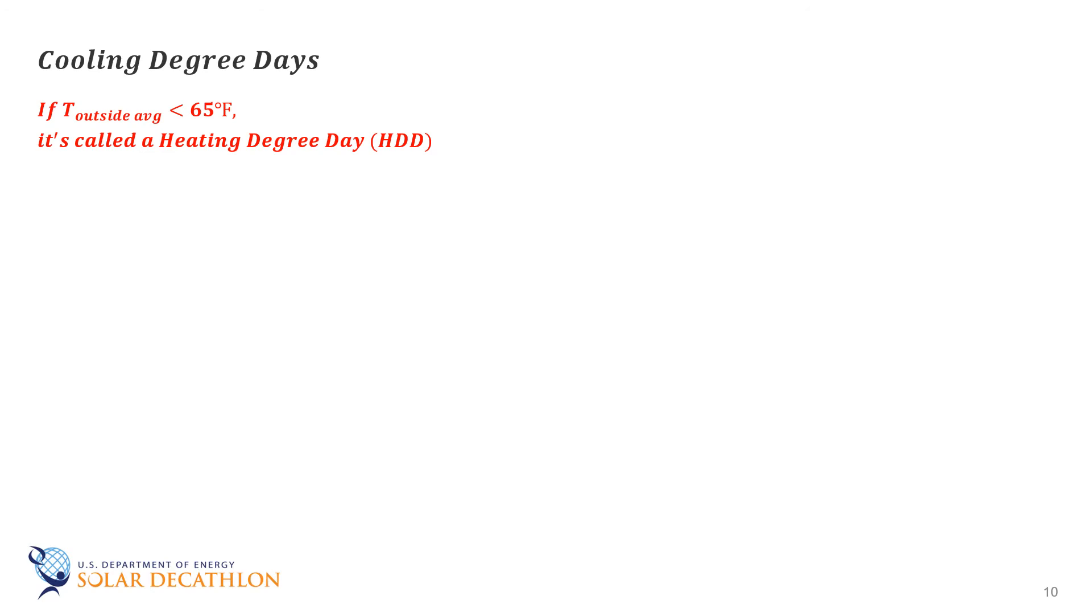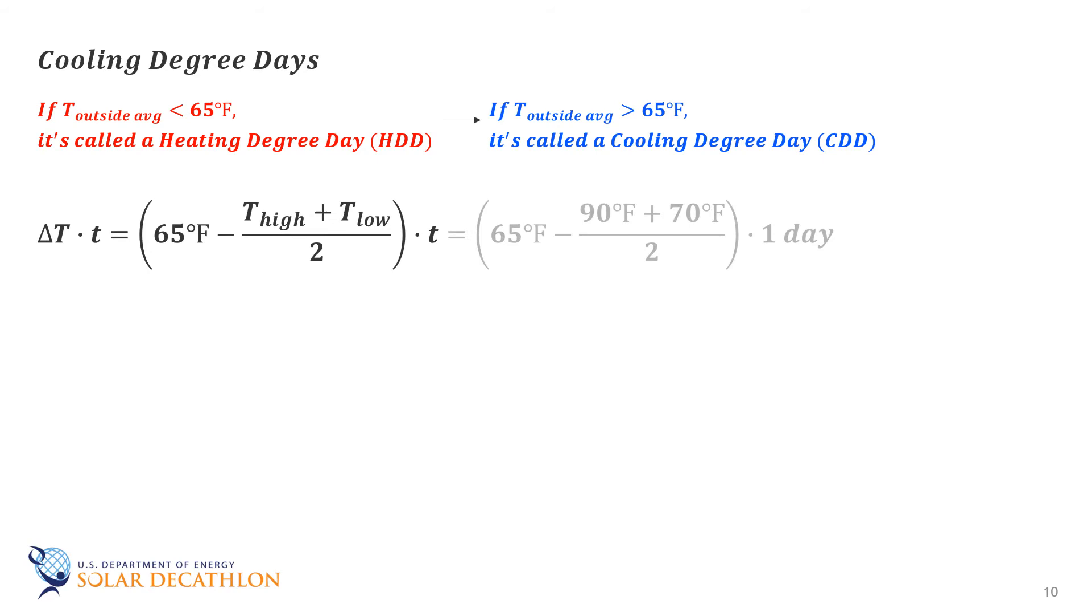Cooling degree days are calculated in a similar manner, except they are tabulated when the average outdoor temperature is above 65. A day with a high temperature of 90 degrees Fahrenheit and a low temperature of 70 has 15 degree F days.